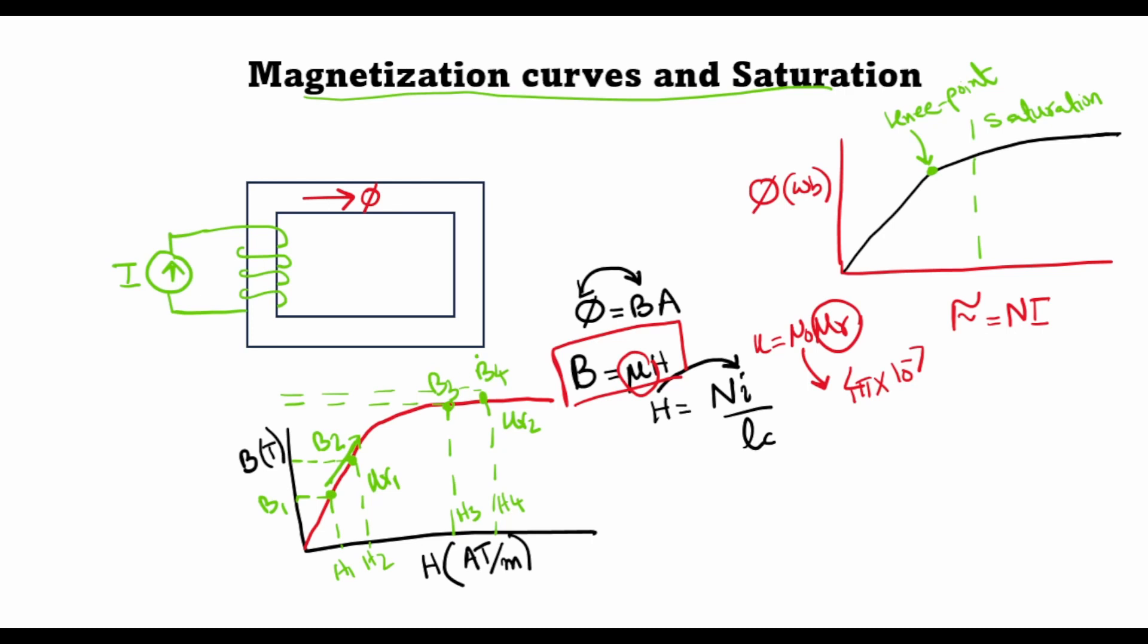Since electrical machines and transformers depend on the magnetic flux to develop voltages, we want the flux to be as high as possible. So it is usually operated very close to the knee point. However, we run the risk of going into saturation if we increase the magnetomotive force further and move into the saturation region.